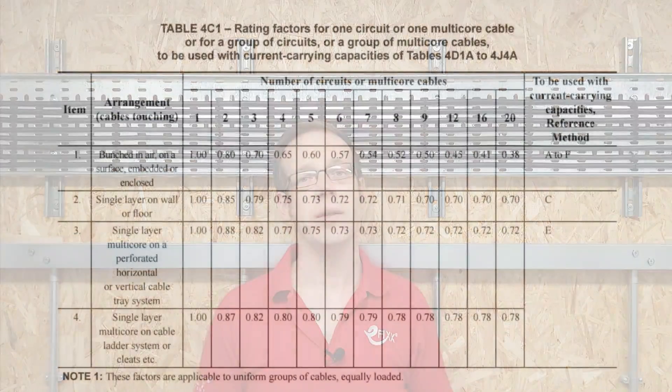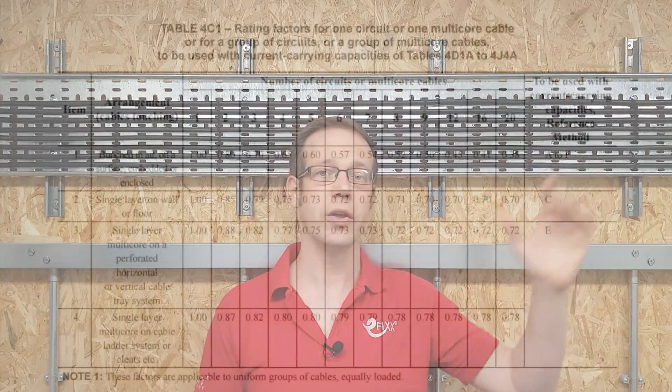Table 4C1 in BS 7671 gives a factor that is used to effectively increase the maximum current a cable must be able to carry, and in reality this results in needing a cable with a larger cross-sectional area. So let's look at an example: if we've got eight cables fixed to a tray feeding eight lighting circuits...